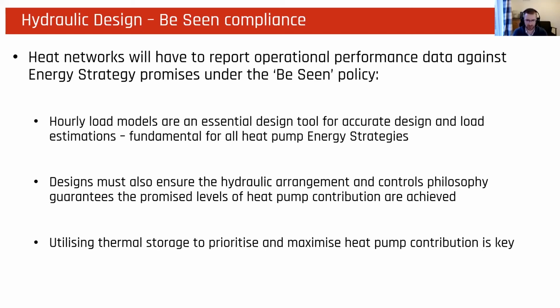And the designs have got to be really well thought out in terms of their hydraulic arrangement of heat pump, thermal store, boilers, buffer, control valves, control logic, and the overall controls philosophy that really gives us that guarantee that we will utilize those heat pumps as much as possible and get that 50, 60, 80, 95%, whatever the energy strategy promises, achieved by the design. If we look at what's happened historically with the CHPs, that simply hasn't happened. But that won't be the case in terms of compliance anymore. So utilizing thermal storage is absolutely key to getting the most out of your heat pumps and not oversizing your heat pumps as well.